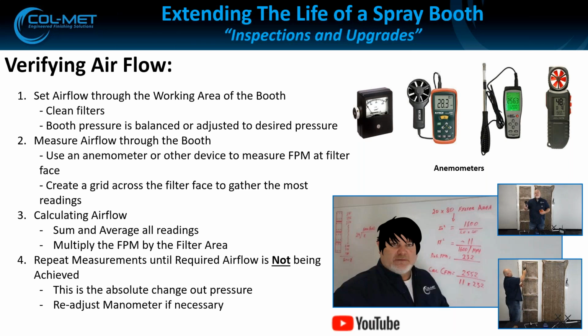If you have a device that's set to run from 100 up to 10,000 FPM, that sweet spot is going to be somewhere around 5,000. If you're not around there, you're going to get some deviation as you go lower or higher. So you need to find a gauge that has a lower range, because honestly, guys, 100 feet per minute or 300 feet per minute is not an extreme amount of air velocity, okay? You have to be cognizant when you pick your gauges that they can get down that low.